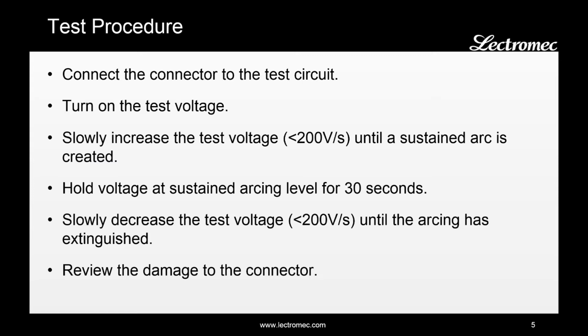The test procedure was to connect the connector to the test circuit and then turn on the test voltage, starting at 0 volts and slowly ramping up until a sustained arc was created. Once the sustained arc was created, we hold the voltage at that level for 30 seconds and then slowly decrease the test voltage until arcing has extinguished. After that's done, we evaluate the damage to the connector.